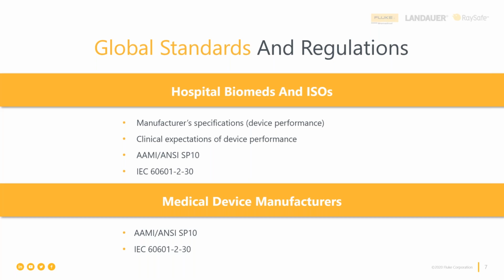Internationally, we look at the IEC 60601 umbrella. We're looking specifically at NIBP in the IEC 60601-2-30. These are written and can be applied in the hospital, but really the first two bullet points that you see here under hospital biomeds and independent service organizations, the ISOs, is the manufacturer's specification for device performance, number one. Because the standards that I've just spoken about apply and are written for the manufacturer to follow, and they have to make measurements and prove in their design validation testing that their way of doing blood pressure measurements in this case is safe and effective for clinical use.